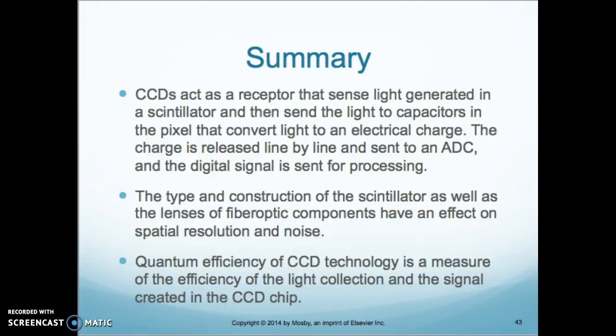CCDs act as a receptor that senses light generated in the scintillator and sends the light into capacitors in the pixels that convert light to an electrical charge. The charge is released line by line and sent to the ADC, and the digital signal is sent for processing. The quantum efficiency of CCD technology is a measure of the efficiency of light collection and the signal created in the CCD chip.